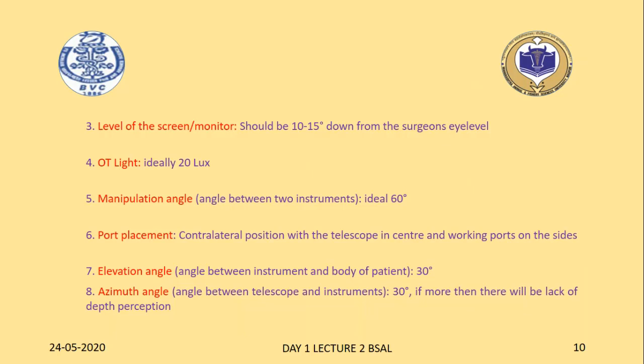So you will find in the first photograph what I have shown is the elbow position in which the patient should be. This is what the height of the patient should be, so that the handle of the instrument is at elbow level. Now, if this is the patient, then the line drawn from the patient and the line drawn from the instrument entering into the abdomen should form 30 degrees. That will make your procedure as good as your normal surgery.